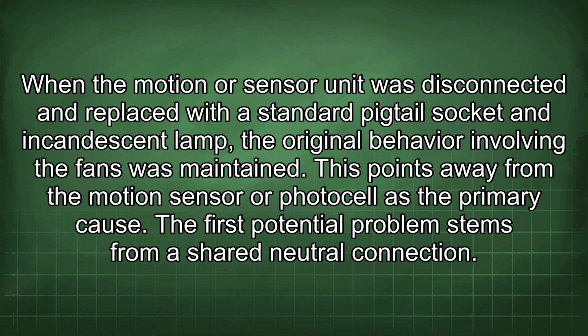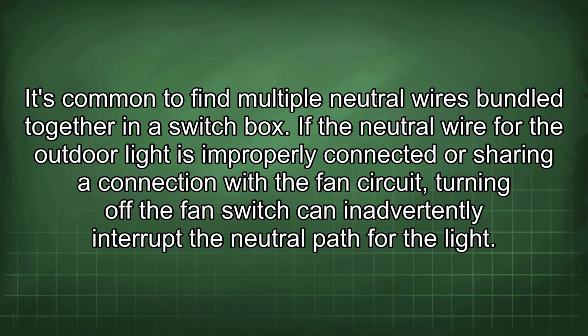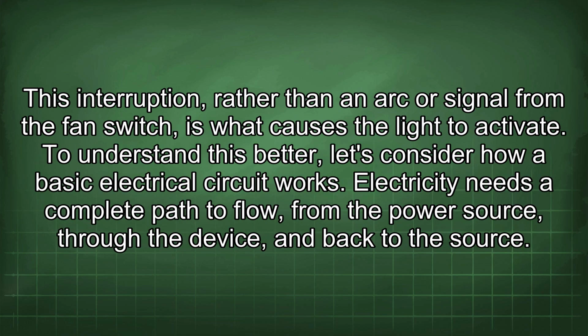The first potential problem stems from a shared neutral connection. It's common to find multiple neutral wires bundled together in a switch box. If the neutral wire for the outdoor light is improperly connected or sharing a connection with the fan circuit, turning off the fan switch can inadvertently interrupt the neutral path for the light. This interruption, rather than an arc or signal from the fan switch, is what causes the light to activate.